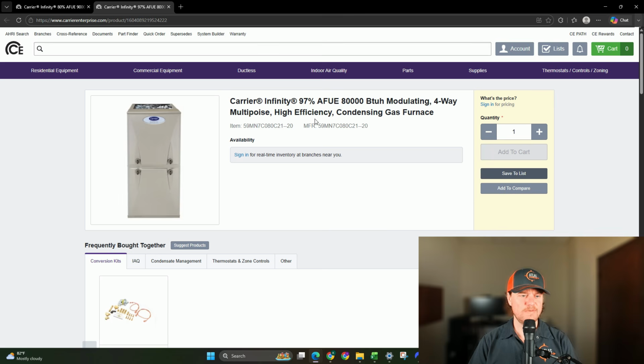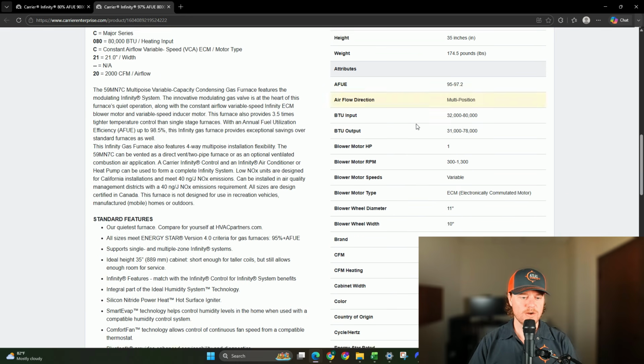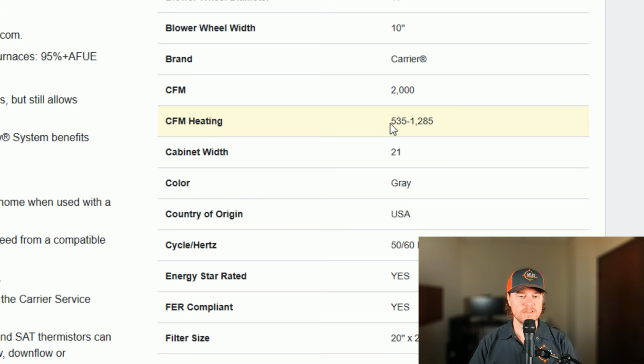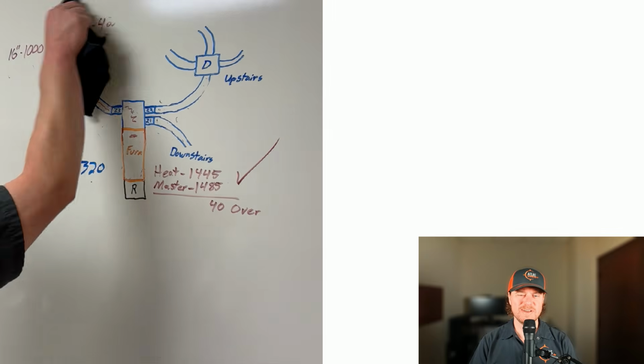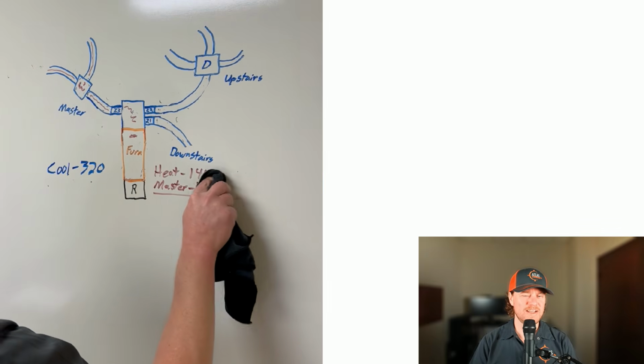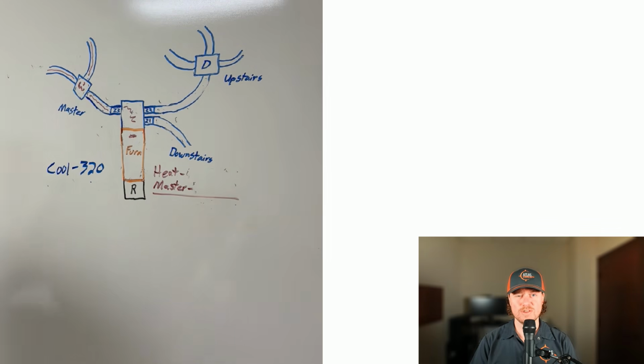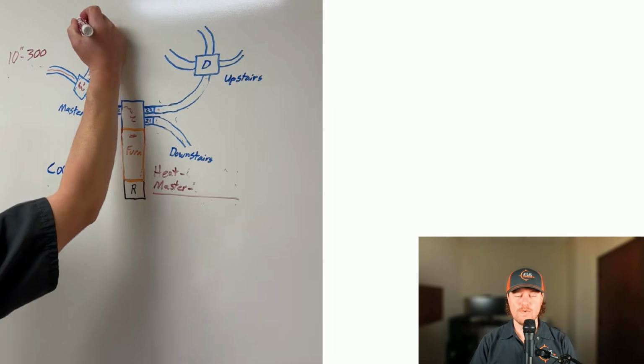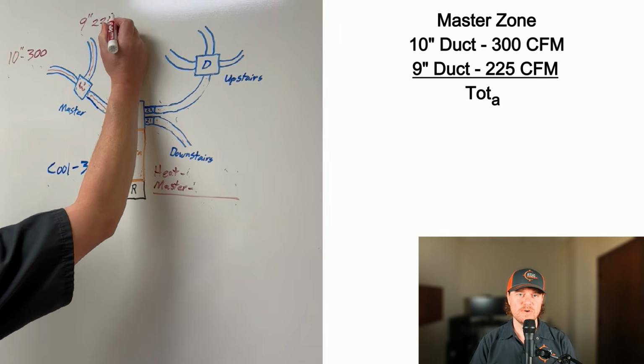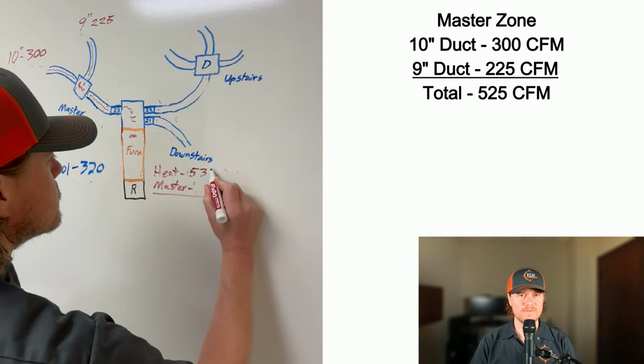This one is a high efficiency 97% furnace. However, the key thing that I'm looking at here is it's modulating. That means it can modulate the heat down to a lower speed. And if we take a look at the heating CFM requirements, you can see that this furnace can modulate as low as 535 CFM and up to 1285 CFM. What this is telling me is I can design the smallest zone down to around 500 CFM without triggering a high limit cutoff. For a 4-ton system, this ends up being around 30% of the operating capacity of the system.